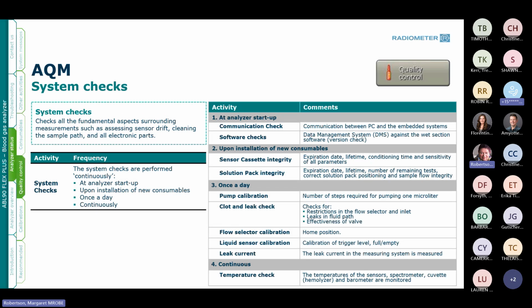So the AQM system checks the analyzer at startup: the communication check is done, software checks are done, and data management upon installation of new consumables. It checks everything on the sensor cassette integrity and the solution pack. Once a day it checks the pump calibration, clot, and leak check. It does a flow selector calibration, liquid sensor calibration, and leak current, and continuous set temperature check. And again, all of these things it does in the background automatically, so you won't see it doing them.